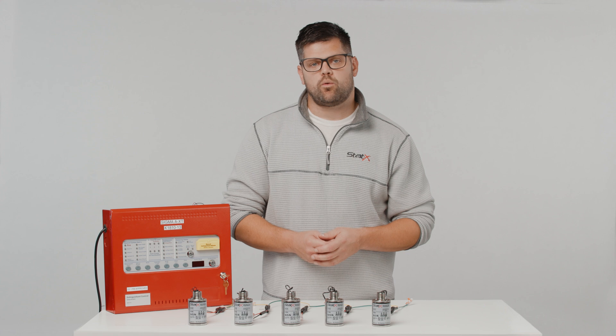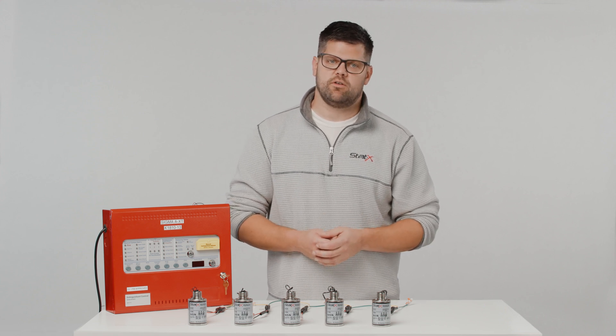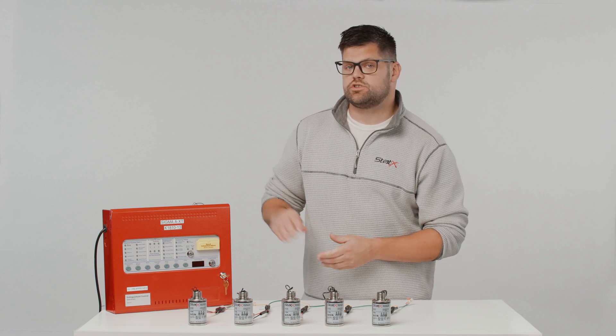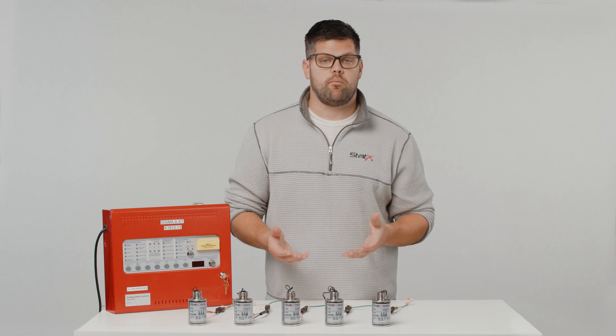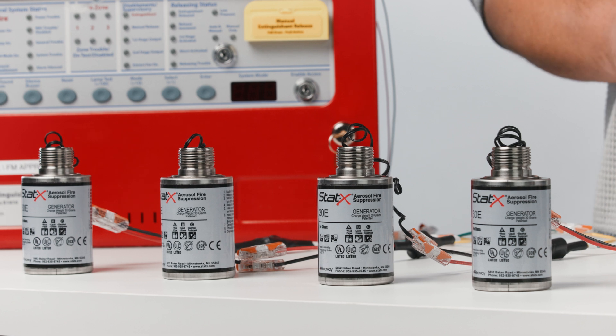There are multiple ways to connect wires, and it's important to use best practices or industry standards in your location. If there is an improper connection, keep in mind this could result in a panel alarm going off, such as a supervisory alarm, or it could potentially charge the capacitor and you may inadvertently fire a StatX device. Therefore, it is imperative that all EPDs be handled in a manner which assumes they will initiate the aerosol generator. I cannot stress that enough.